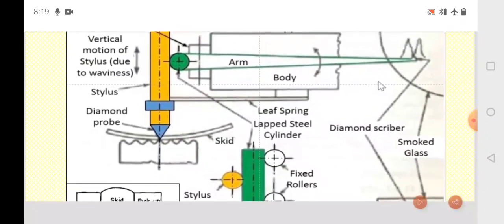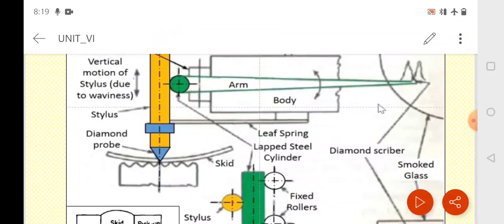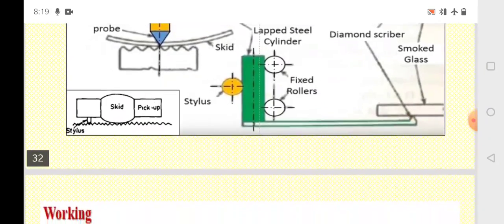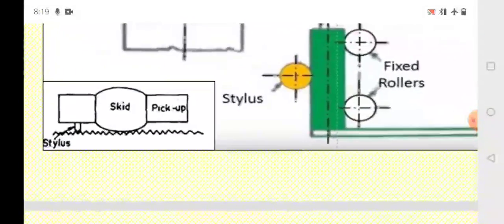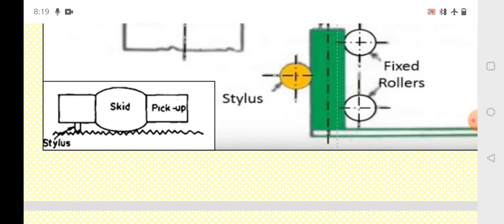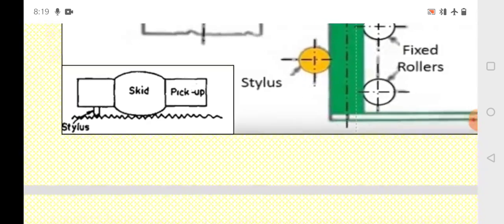So there is a skid before this diamond probe. First this skid is moving and then this diamond probe is moving, as you can see in this diagram. This diamond probe is very precise and costly, and it should not get affected by the roughness. So this is a pilot which will move ahead first and then this diamond probe is moving. So this is the skid and then this stylus is moving behind it.